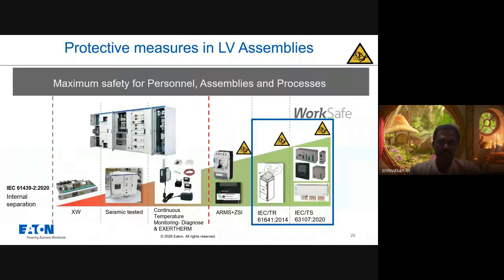So how can we improve the safety of the switchgear? Basically, any switchgear is expected to be type tested to IEC 61439-2, which ensures proper internal partition. We can also improve safety by having a completely withdrawable cubicle system. The switchboard can also be seismic tested, meaning earthquake tested. We can also have preventive measures.